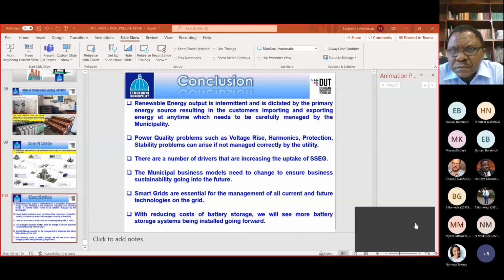That's a good question. What I showed on the graph was a typical customer, a typical mall within the municipal network, not a large IPP farm, because those are contracted and you want them on the grid. But in terms of safety on the local network, typically you want anti-islanding. You want the customer to switch off so he can't backfeed and hurt or kill people working on the network. There are cases where the customer will disconnect from the network and run in island mode, but he first has to disconnect before going that route, if they bring in standby generators and then bring in the PV, etc. I'm not sure if that's clear.